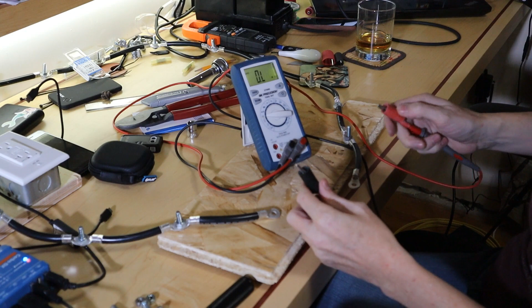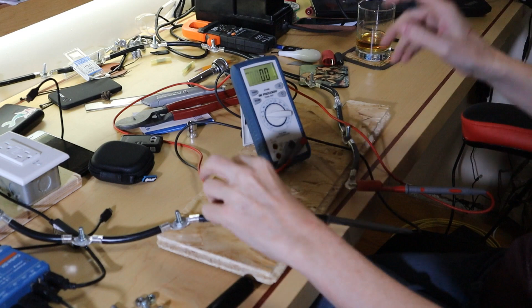One's going to be the solid bus bars and one's the flexible bus bars. I'm using alligator clips because they apply consistent pressure on the two ends. All the bolts are torqued together. I have my 15 jumpers, matching the 15 bus bars, and let's see what we get for measurable resistance — I'll leave it on until the number stabilizes.